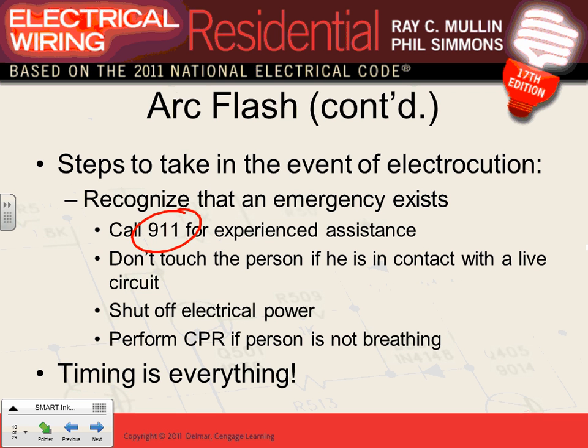The last thing you want to do is grab on them, because you'd become part of the electrical circuit and die too. You need to de-energize them as soon as you can, the proper way, by knowing where the disconnect is. That's why OSHA has rules for working energized. When you have an energized work permit, part of it requires identifying all sources for disconnecting power, so if someone working energized gets electrocuted, you can walk to the source and disconnect it immediately. That permit requires at least six people to sign off, including your manager and maintenance.